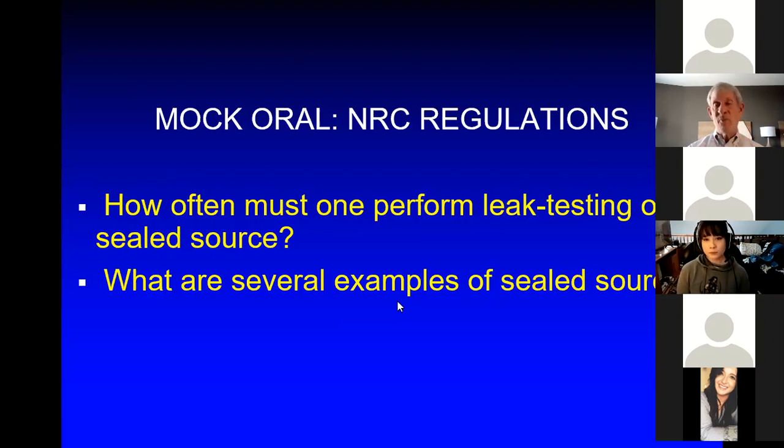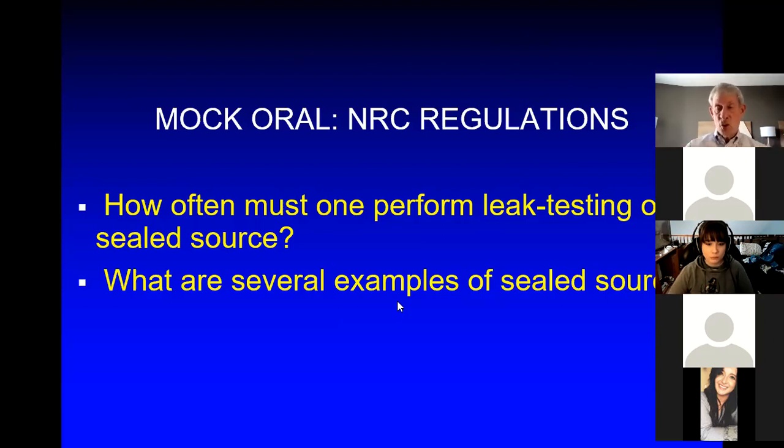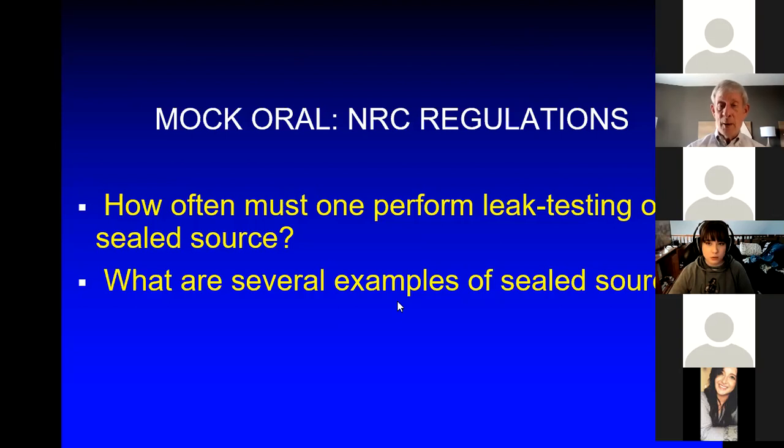And what about physically the largest one of all? It might be a very large rectangle or a very large circle. Your flood source. Sure. So our cobalt 57 flood sources, they're sealed. They are made by taking liquid Lucite, which is homogeneously filled with cobalt 57. They pour it into a mold.